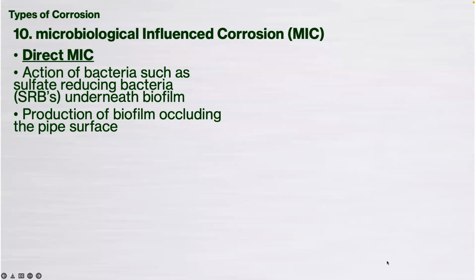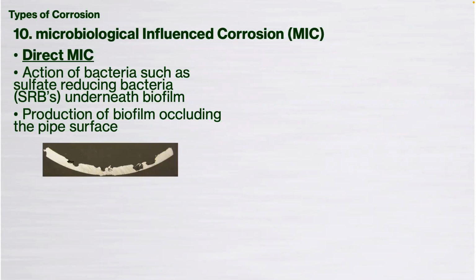But that biofilm, that slime, lays on the pipework surface, and as a result, your inhibitor can't get to the surface to protect it, and underneath is your bacteria munching away at your pipework. Sometimes iron bacteria that will literally eat the iron pipework. And of course, your inhibitor cannot get to the metal surface, and therefore you start having corrosion at the points where there is inhibitor and where there isn't. So we need to look out for bacteria. This is some thin-walled pipework from the UK that looks like Swiss cheese, just to give you an idea what the bacteria have done to that piece of pipework.